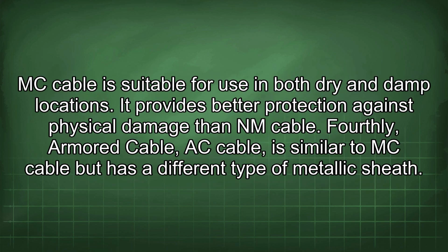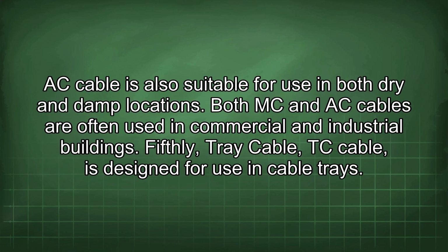MC cable is suitable for use in both dry and damp locations. It provides better protection against physical damage than NM cable. Fourthly, armored cable, AC cable, is similar to MC cable but has a different type of metallic sheath. AC cable is also suitable for use in both dry and damp locations. Both MC and AC cables are often used in commercial and industrial buildings.